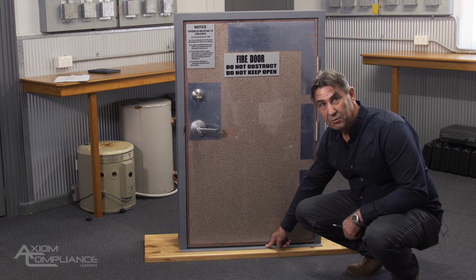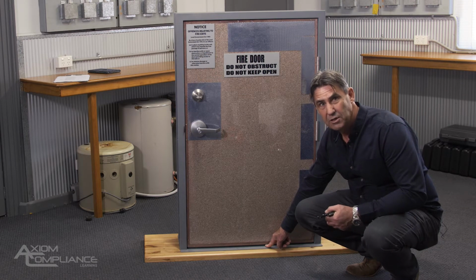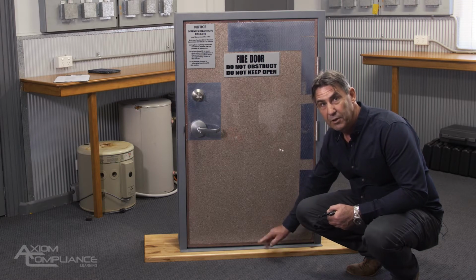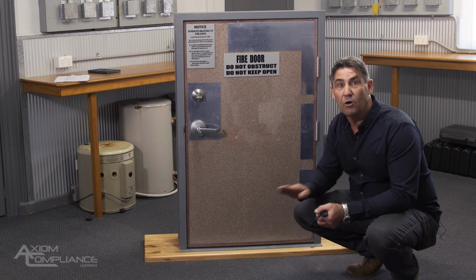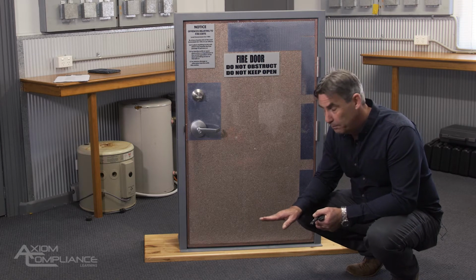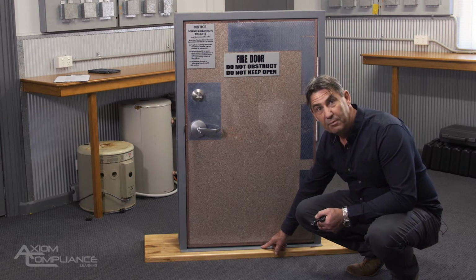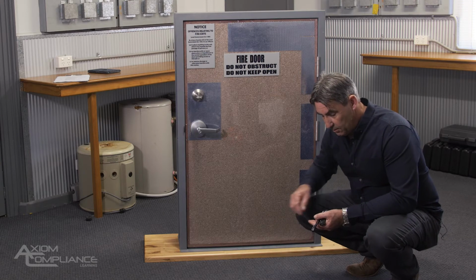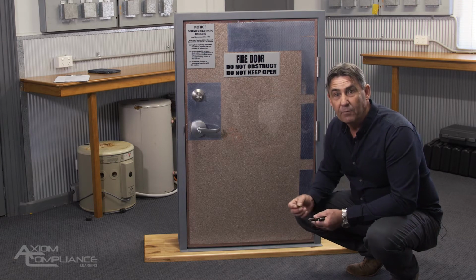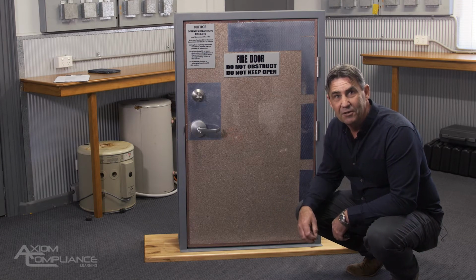And there's an additional requirement to make sure that from the hard surface or the non-combustible surface, you have no more than 25 millimeters. From the non-combustible surfaces, which may be concrete underneath carpet, for example, 25 millimeters from there to the bottom of the door. So there are a number of slides and checks that you can use.